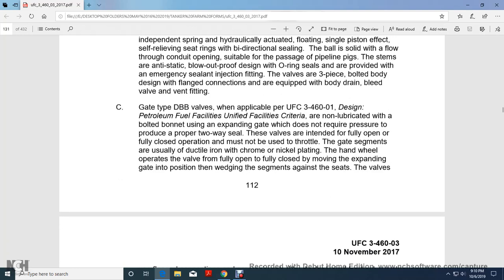Gate valves with a double block and bleed valve, when applicable under UFC 3-460-01, Design: Petroleum Fuel Facilities, Unified Facilities Criteria, are non-lubricated, bolted bonnet, using an expanded gate that does not require line pressure to produce the proper two-way seal. The valves are intended for fully open or fully closed operation. Must not be used to throttle.